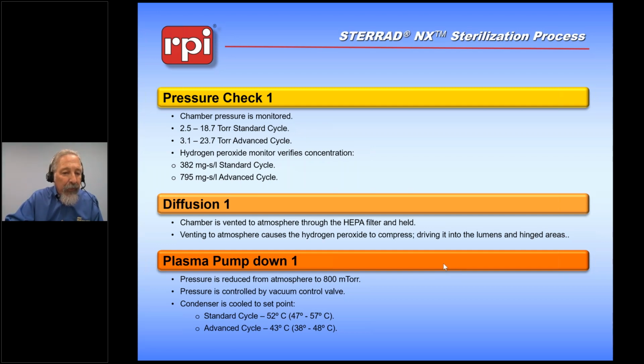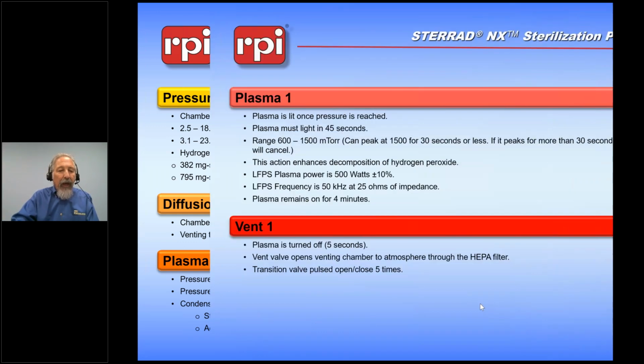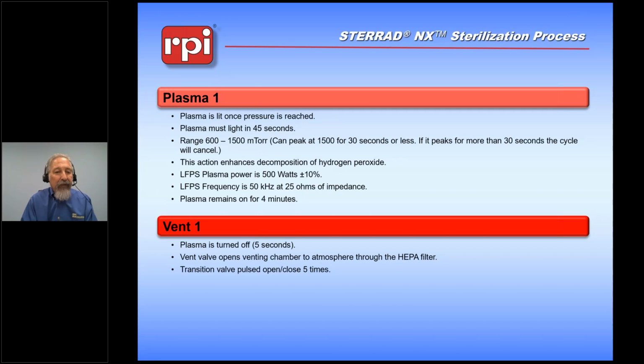Once we're ready with the plasma pump down, we then turn on the plasma, which spreads through the entire material in the chamber, and that plasma must light within 45 seconds. The machine can tell when the plasma is lit, and during the process of generating the plasma, we will also pull a much more solid vacuum, making sure that we have all of that peroxide where it can go. We want to be sure it's completely diffused.